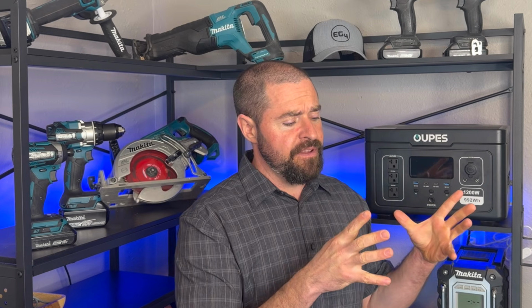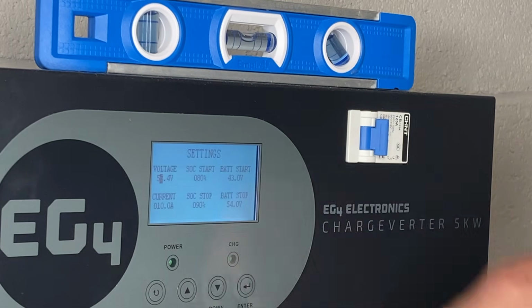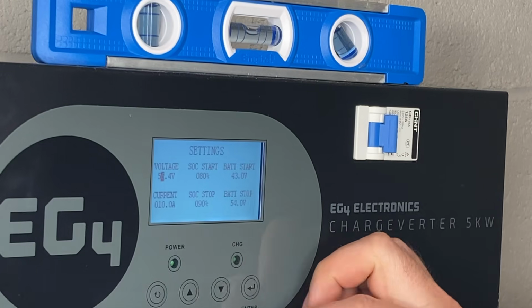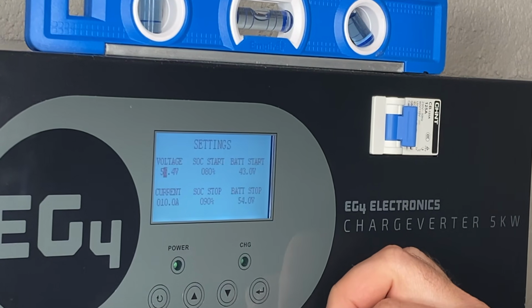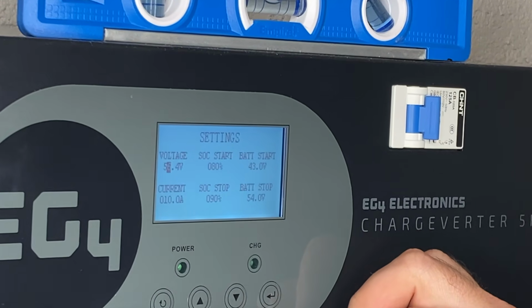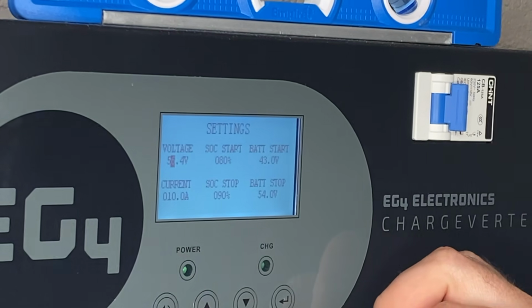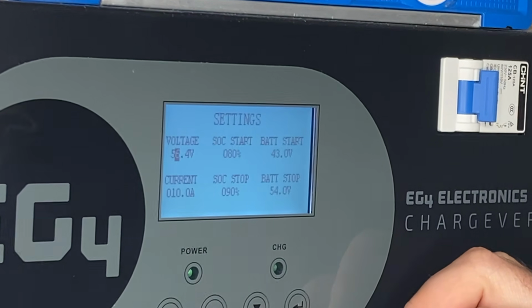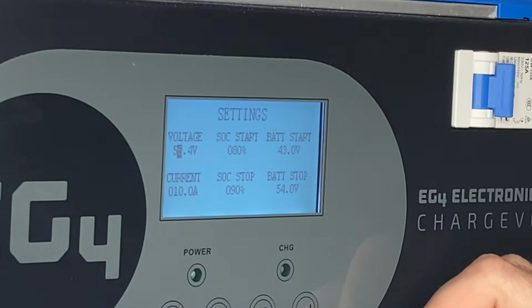What happens when those generators get overloaded is they have voltage fluctuations and send dirty power into your home, which can cause damage. So rather than tying it into the generator port, you want to get yourself an EG4 Chargeverter. You tie the generator into the Chargeverter, and that Chargeverter cleans up that power and turns it into DC current that goes directly into your batteries rather than into your home. That protects your investment from that dirty generator power.